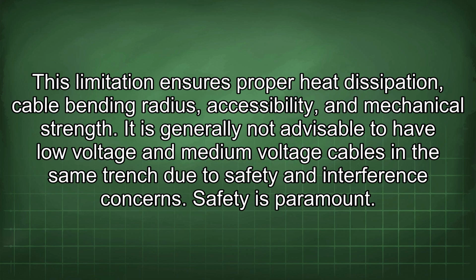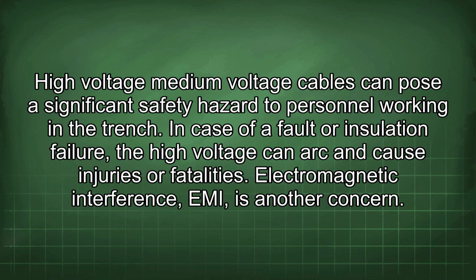It is generally not advisable to have low voltage and medium voltage cables in the same trench due to safety and interference concerns. Safety is paramount. Medium voltage cables can pose a significant safety hazard to personnel working in the trench. In case of a fault or insulation failure, the high voltage can arc and cause injuries or fatalities.